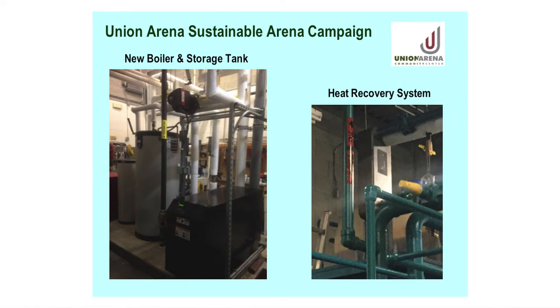So what we tried to do is start to recapture some of that heat, and we'll do more of it in later phases, so that now, through this system, we're capturing literally millions of BTUs each day off the compressors and putting it into the building heat systems. It's a pretty straightforward strategy, tricky to pull off though.